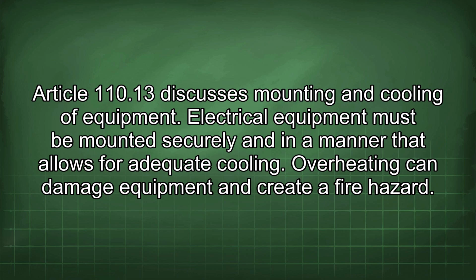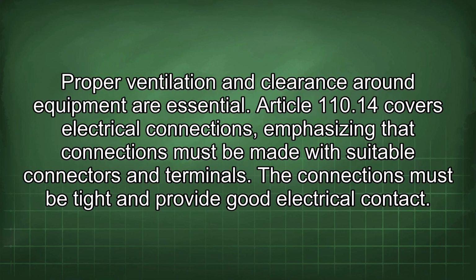Article 110.13 discusses mounting and cooling of equipment. Electrical equipment must be mounted securely and in a manner that allows for adequate cooling. Overheating can damage equipment and create a fire hazard. Proper ventilation and clearance around the equipment are essential.